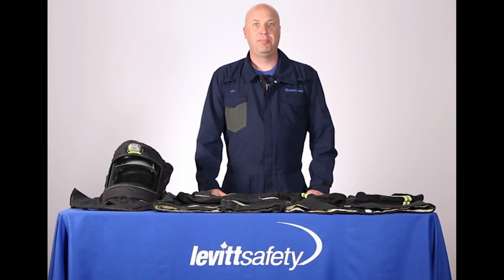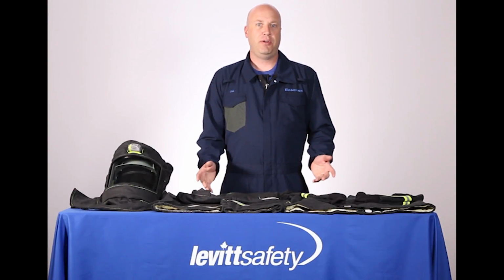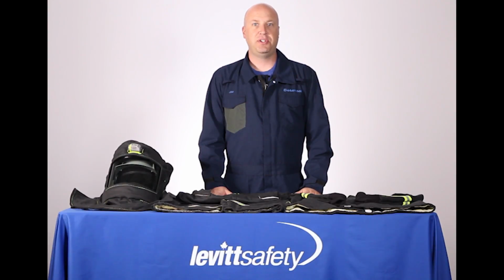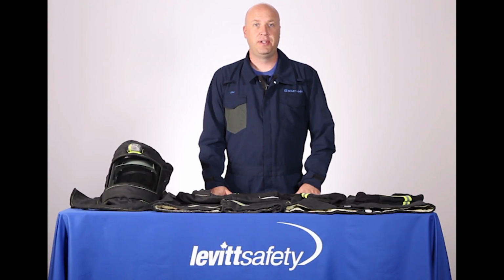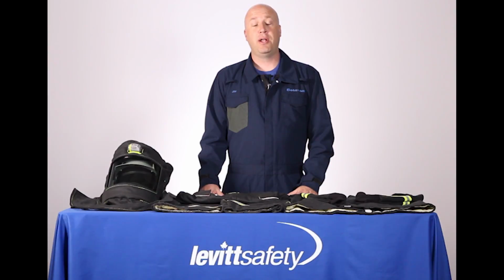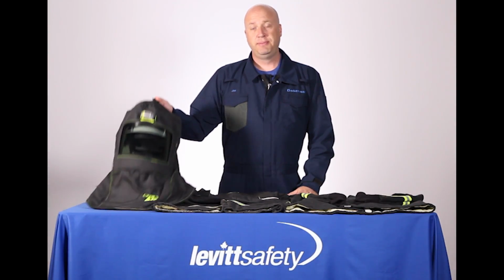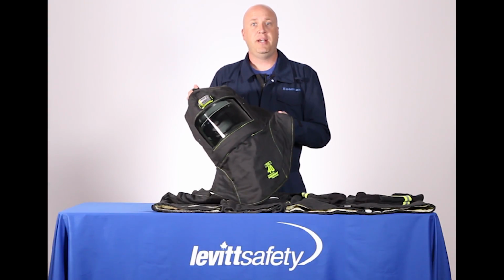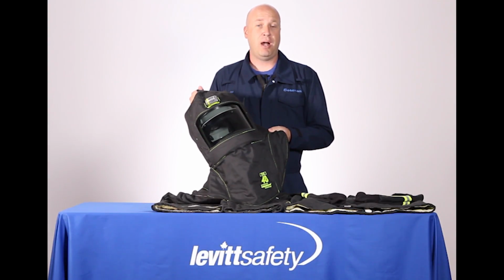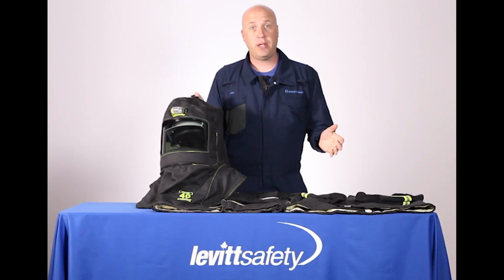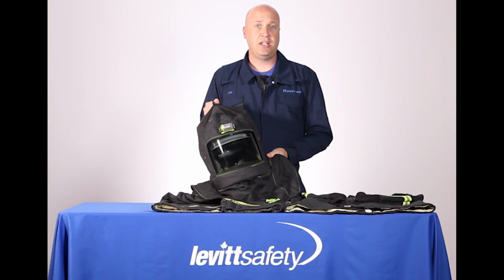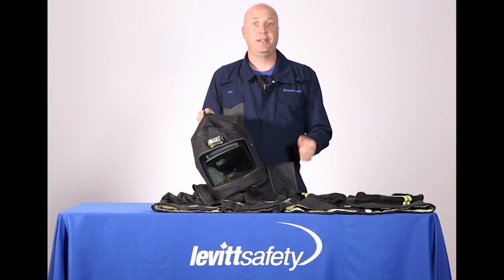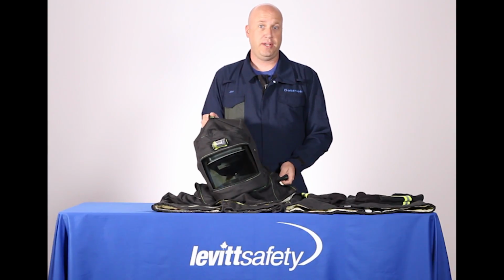Workers are required to complete a pre-use inspection of all of their electrical specific PPE tools and equipment, including their arc flash suits. When inspecting your Oberon arc flash suit, start with one item at a time. I begin with the hood. We want to make sure that the fabric has no damage. If you identify a problem or an issue at any point in your pre-use inspection, do not proceed to use the product until it has been cleaned, repaired, or replaced.